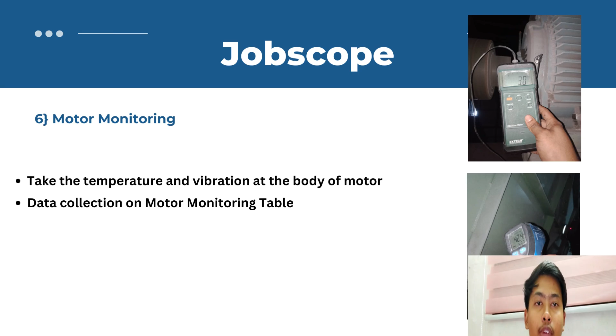We monitor the motor by taking the temperature and vibration at a few points of the motor. A good temperature is below 70 Celsius. We take the vibration and temperature at the bearing forward, bearing secondary, and body of the motor.